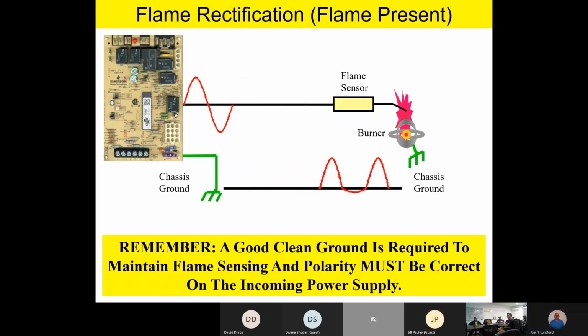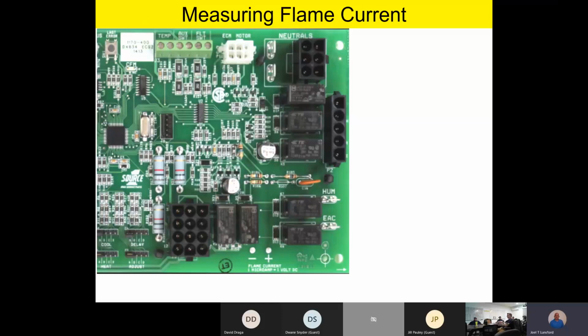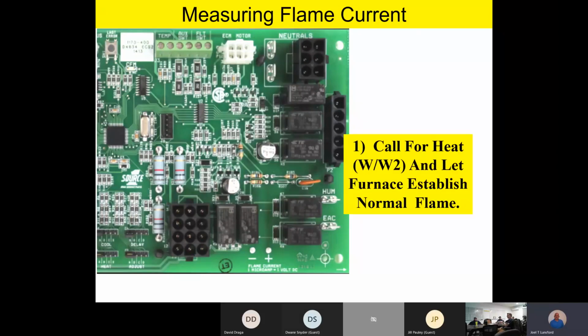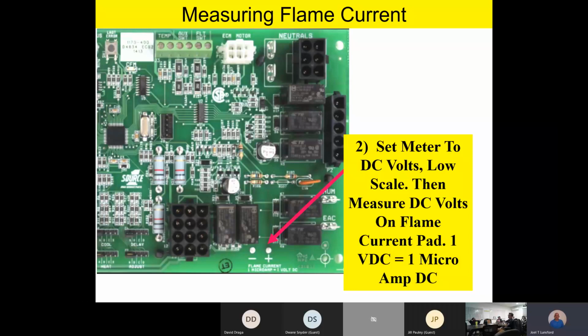And measuring flame current, what you're going to do is call for heat and let the furnace establish normal flame. It doesn't matter if it's first or second stage heat. Then take your voltmeter and set it to DC volts. I recommend a lower scale because it's going to be a fairly low number. Then measure your DC volts on the flame current pad. Now remember, team, 1 volt DC equals 1 microamp DC. Please write this down and remember it.